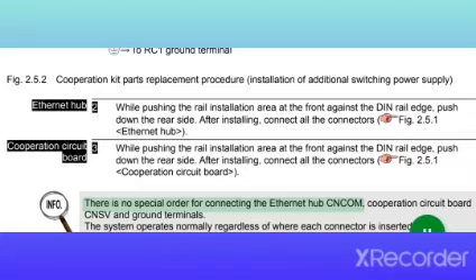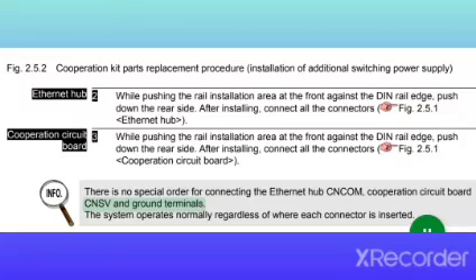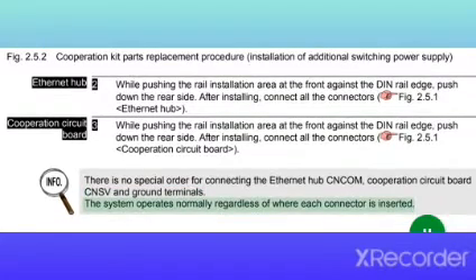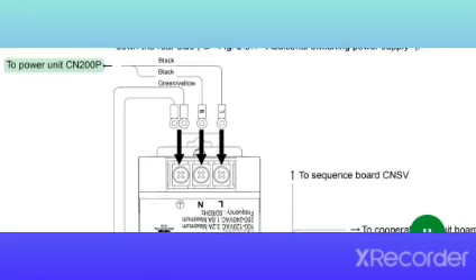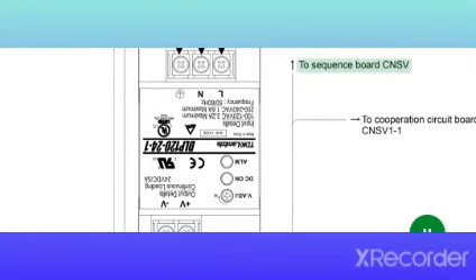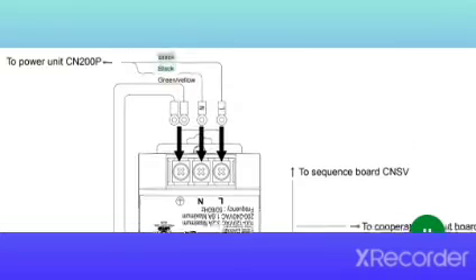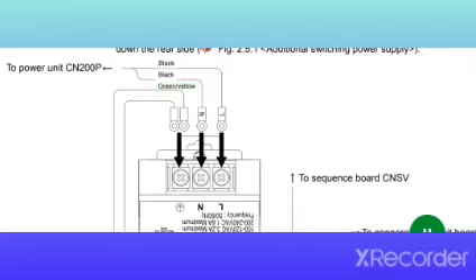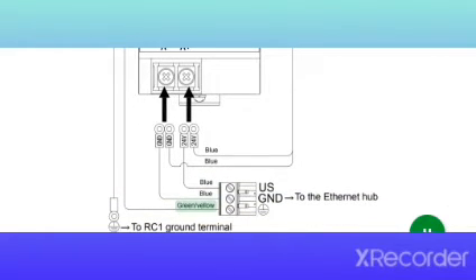Info: there is no special order for connecting the Ethernet hub CNCOM, cooperation circuit board CNSV and ground terminals. The system operates normally regardless of where each connector is inserted. To power unit CN200P; to the Ethernet hub; to sequence board CNSV; to cooperation circuit board CNSV1-1; to RC1 ground terminal. Black, green/yellow, blue.